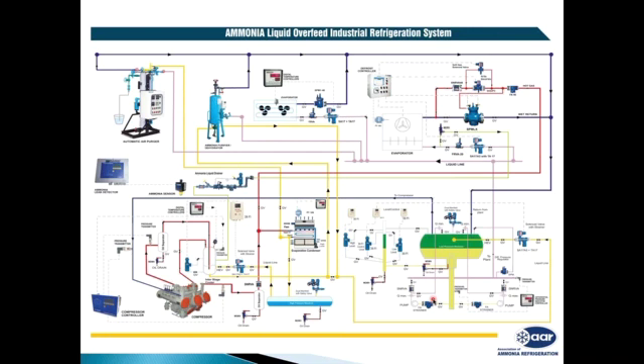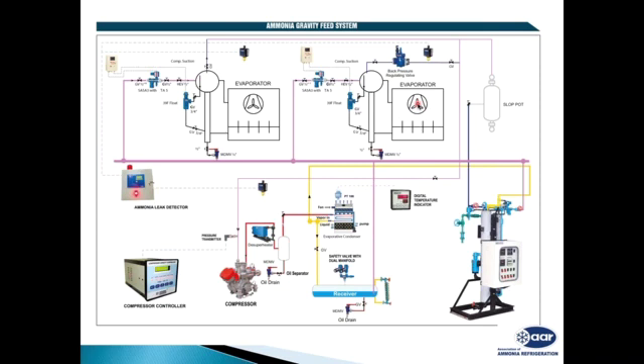As we know, there are two types of systems mostly popular in ammonia refrigeration in India and abroad. One is ammonia overfeed system or ammonia pump circulation system, in which ammonia is circulated through the pump, and another is a natural circulation or a gravity feed system, in which ammonia is circulated up through the system by the pressure difference. This is because of the pressure difference that high pressure in the receiver travels to the low pressure side of the evaporator. There is a reason this is called the gravity system or the natural circulation system.